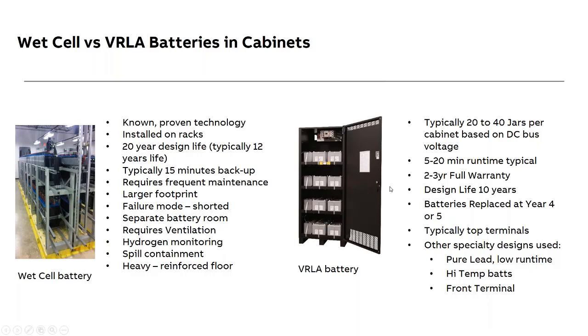Lately, we have seen some pure lead versions instead of the lead calcium, of the lead acid, because the battery is essentially just the gap filler. When power fails, the generator starts and it's up and running in less than 20, 30 seconds in most data centers. If it's a hospital, it's less than 10 seconds.